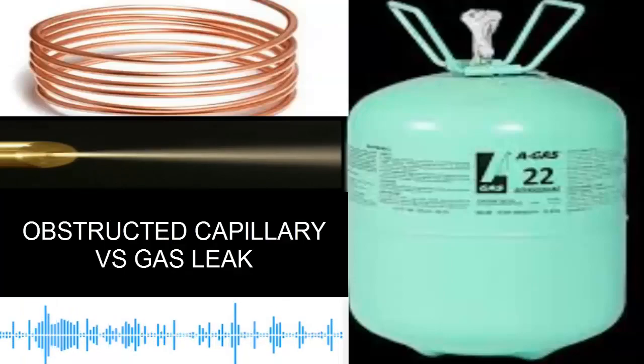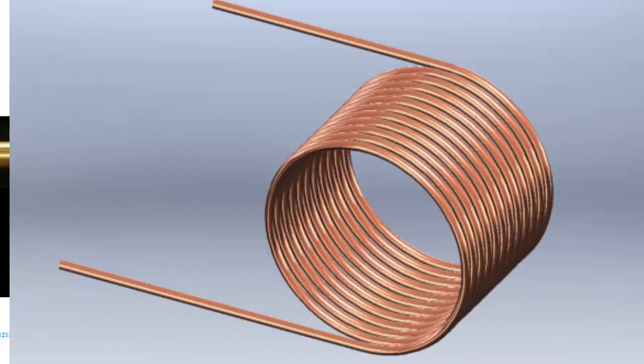D. Some air conditioning systems have more than one capillary. If one capillary is obstructed, you will notice that it is wet or cold, while the other capillaries will be at normal temperature. This indicates an obstruction in the problematic capillary.